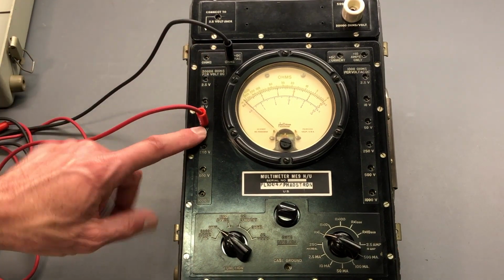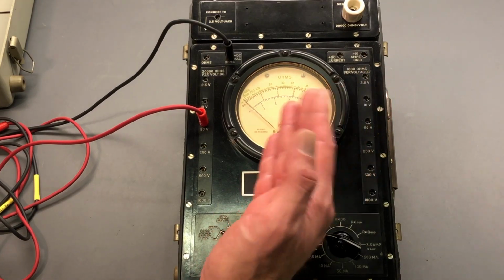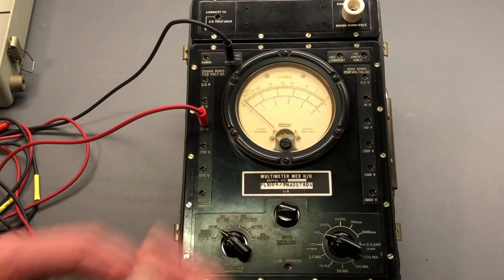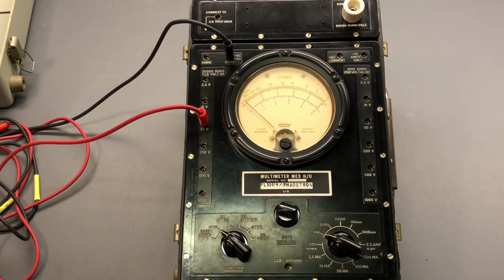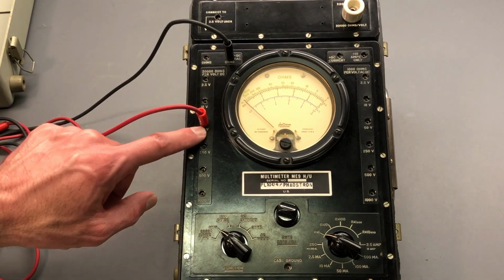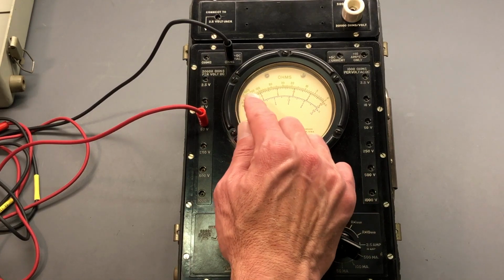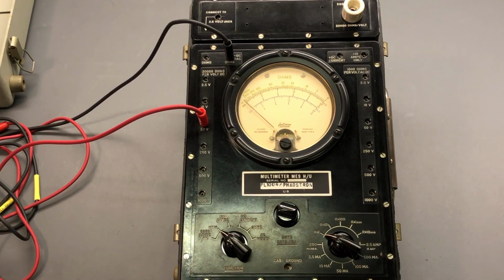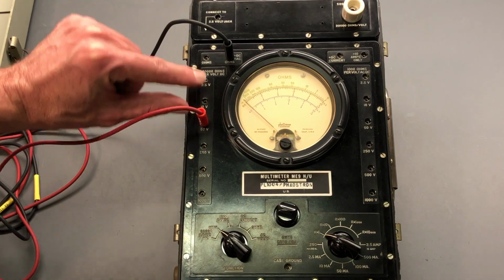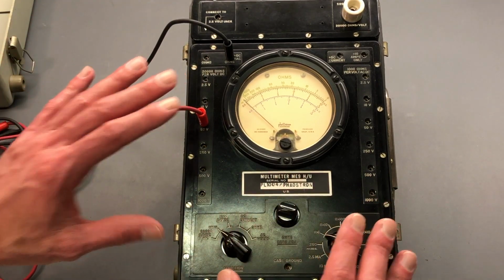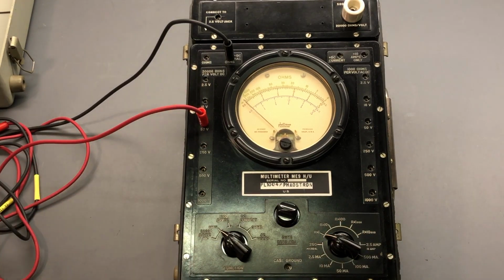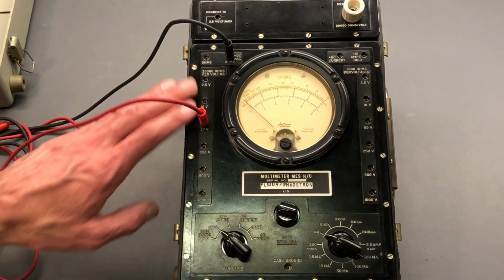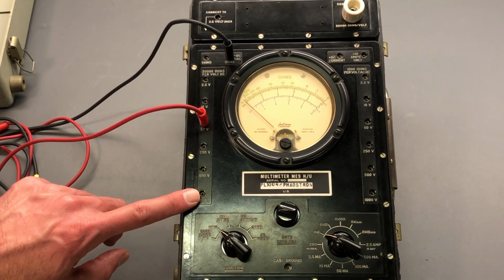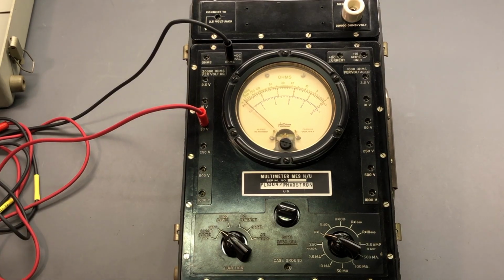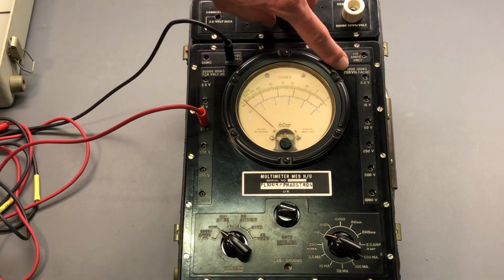Now, if you apply more than 50 volts, this would indicate beyond full scale, and if it's extremely beyond 50 volts, there is a possibility of damaging the meter movement. So again, keep that in mind. If you have, let's say, 1 volt, 3 volts, 5 volts, something very low, and you're on the 50 volt setting, you'll only get a very small deflection, very difficult to make any meaningful or accurate reading. So if that happened, then you would want to move this down to 10 or 2.5 as appropriate. If you have no idea what the voltage is, you would start at 1,000 and work your way down, okay? So it's, again, a manual ranging. It's up to you to select the appropriate range and always start at the highest range and work your way down if it's unknown.